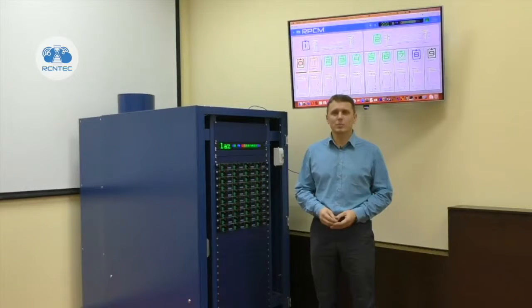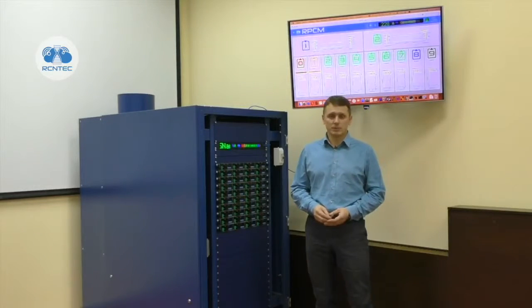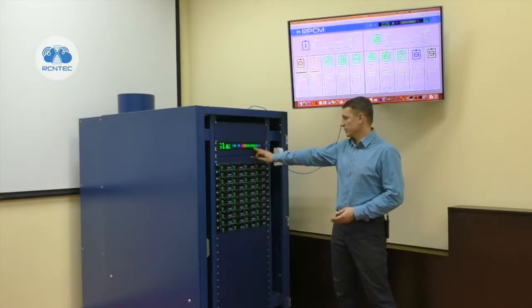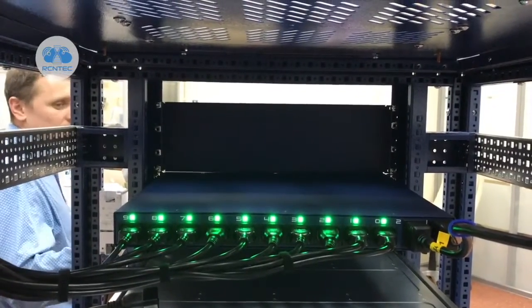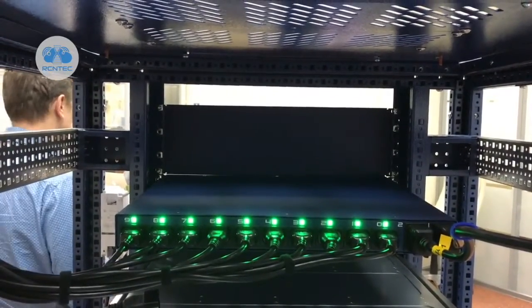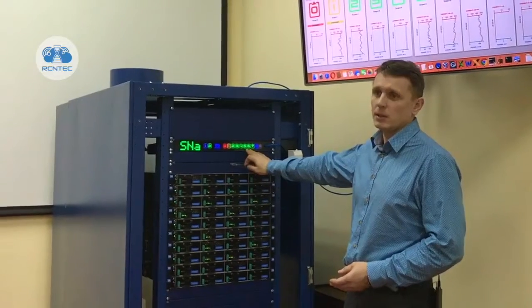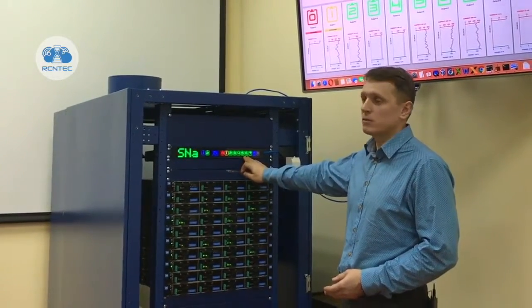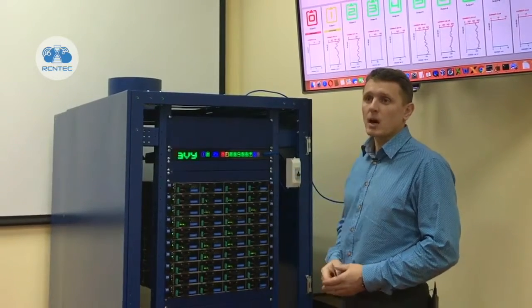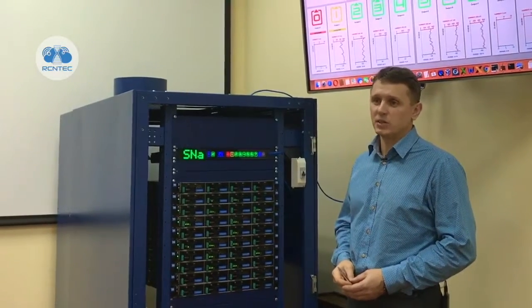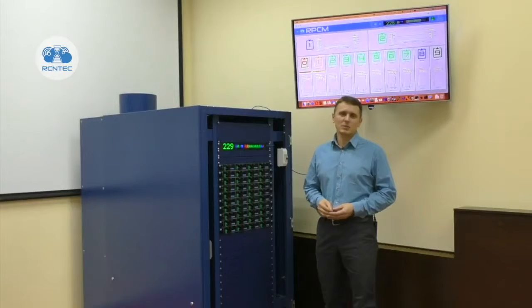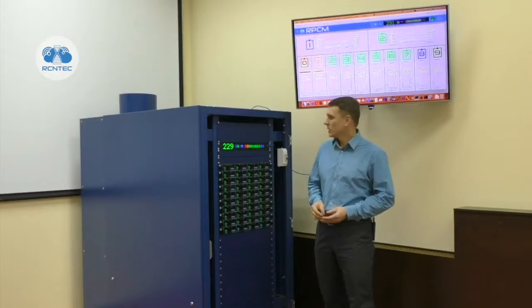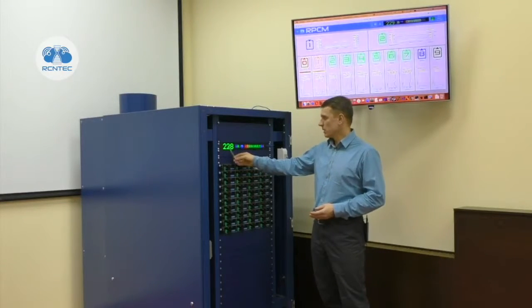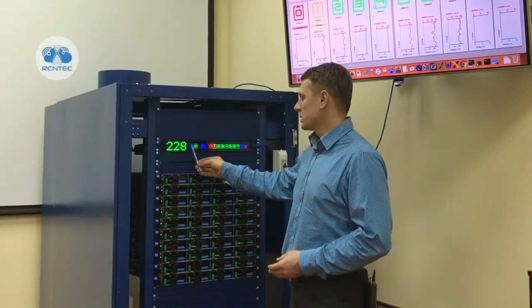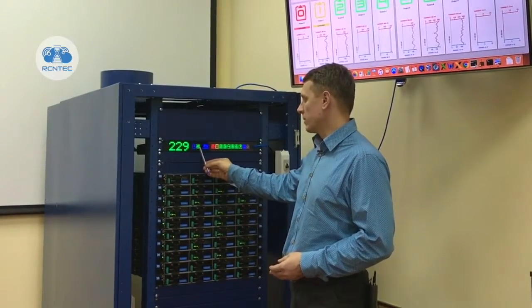Moving on to the RPCM itself. It's a single rack unit module. On its back, there are 10 outlets for connecting consumers and 2 independent inlets with automatic transfer switch or ATS functionality. On RPCM's front panel, you can see the information display with color status indication for inlets and outlets.